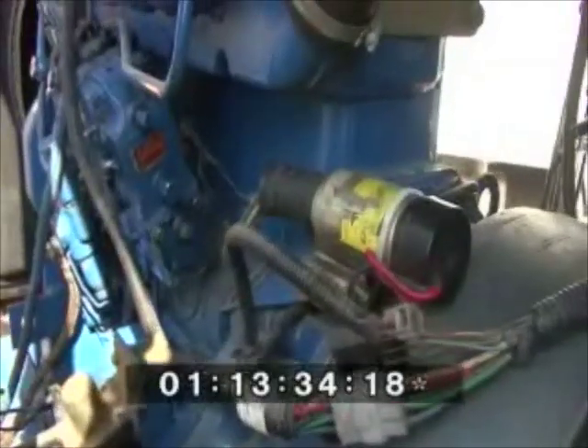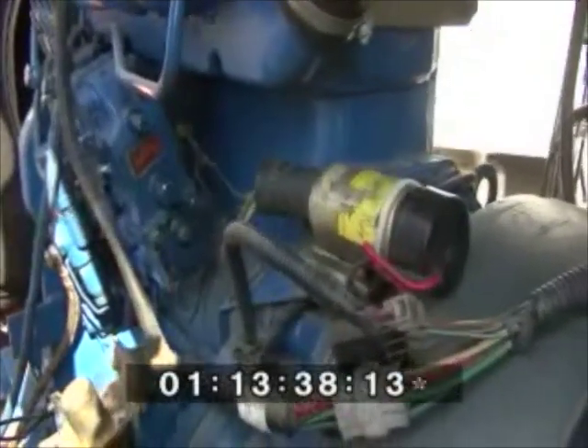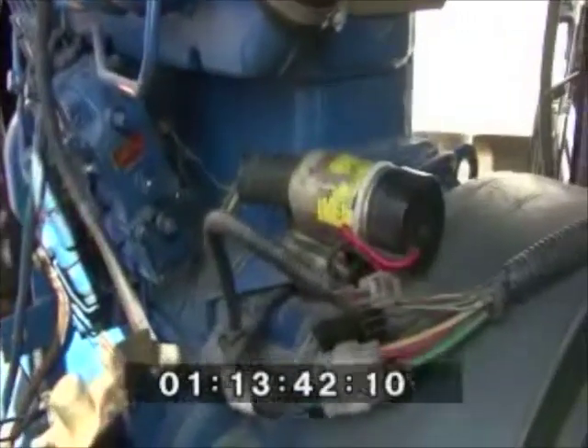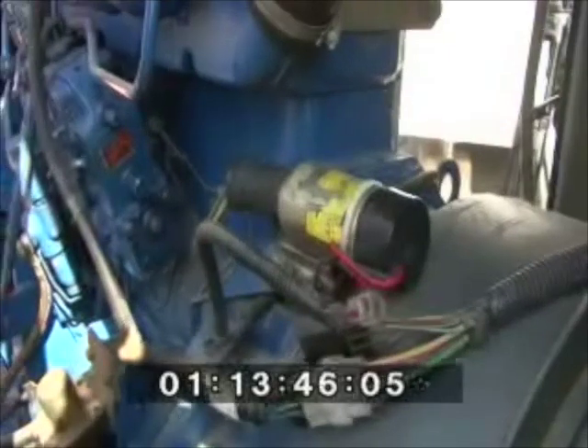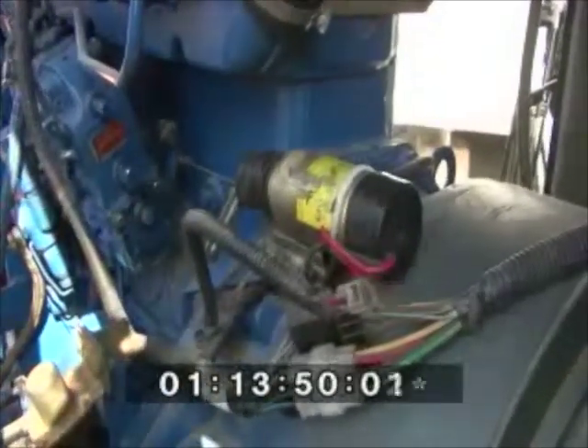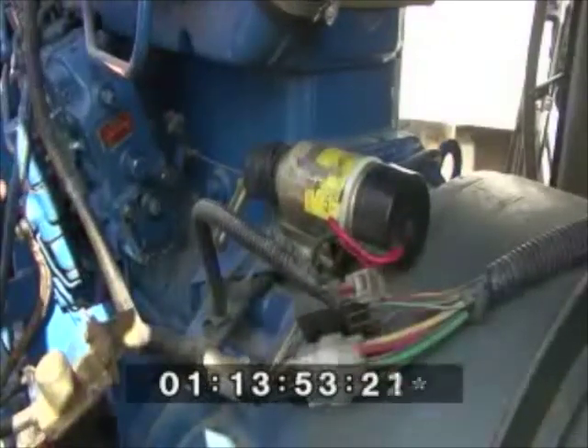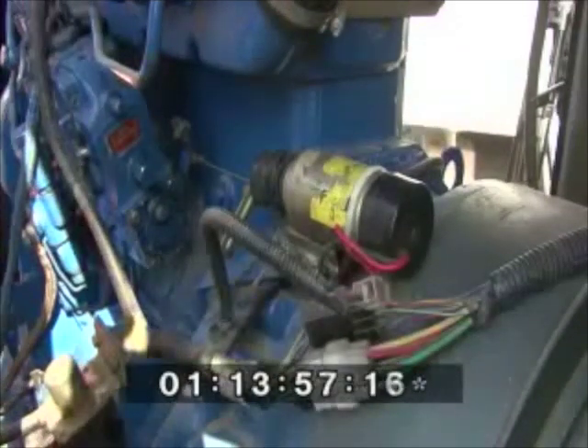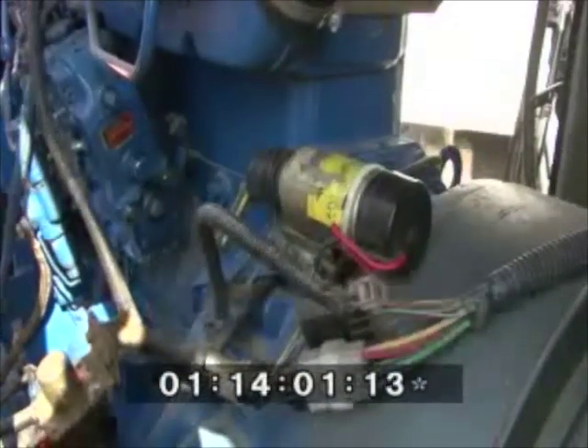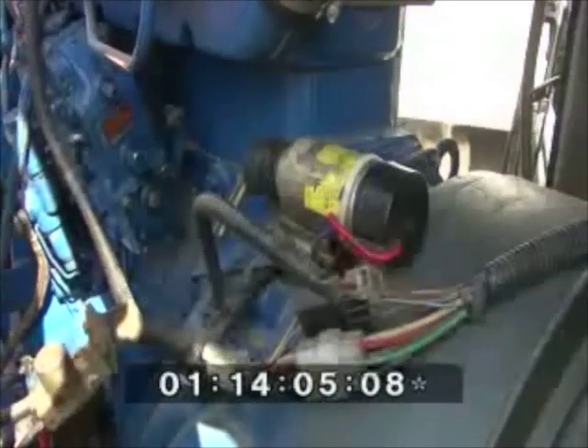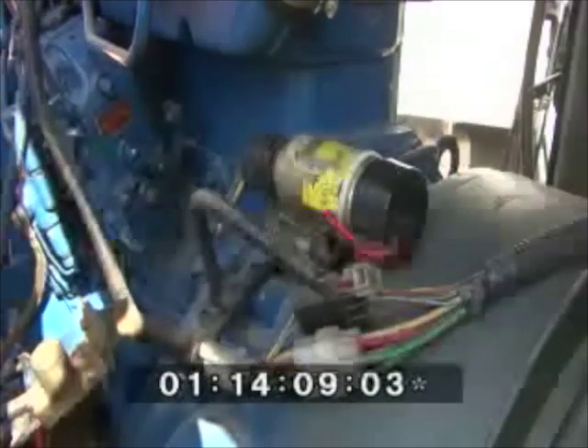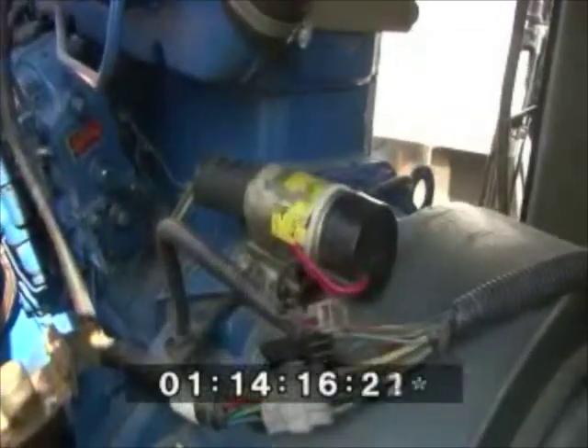This stop solenoid switch cuts off the fuel from getting into the fuel pump of the DG, and the DG stops working. We will now start the DG, and you can see the DG is working. We will now press the stop button. You can see the stop solenoid switch contracts and the DG stops working. This works on the magnetic field. When activated, it retracts back due to the magnetic field and stops the fuel from getting into the pump, resulting in stopping the DG from working.